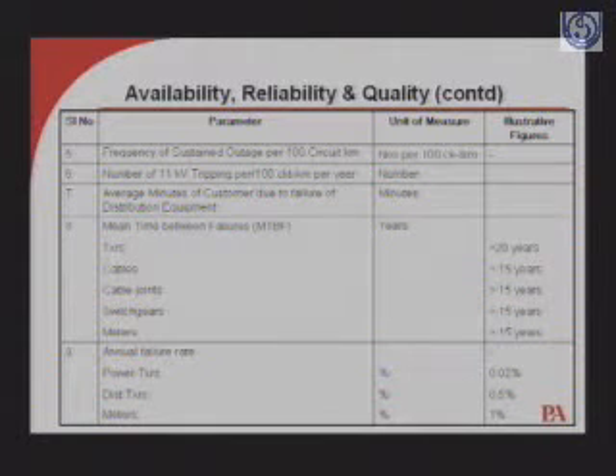Number of 11 kV trippings per 100 circuit kilometers. Same thing, momentary tripping. Average minutes of customer outage due to failure of distribution equipment. The customer supply can be affected either by failure of the distribution equipment or failure of the line. We have talked about the failure of the line. Now, there can be an instance where the distribution equipment has failed and customer supply is being affected. We can always calculate that.